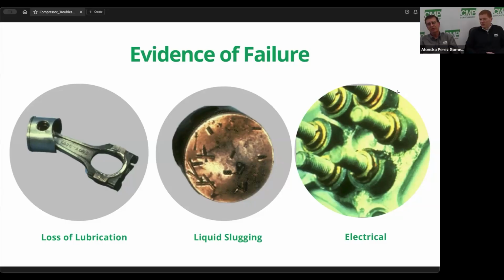Yeah. And if your compressor is not burnt on a semi-hermetic compressor, close your suction and discharge valves, front seat both of those. And then, when you change the compressor, all you have to do is pull a vacuum on the compressor itself.